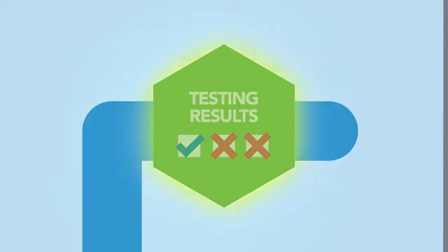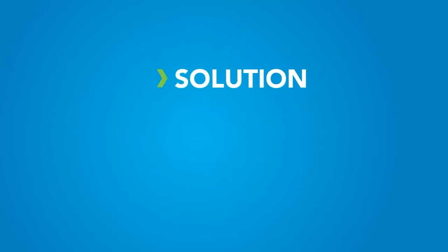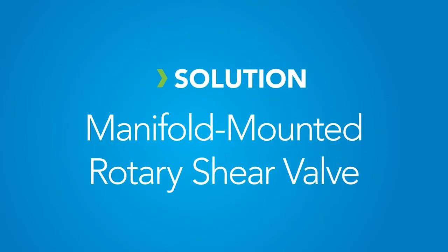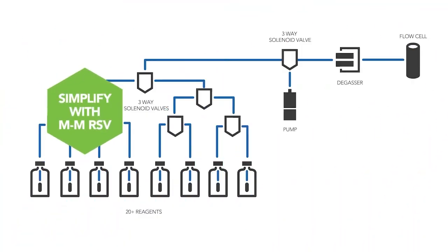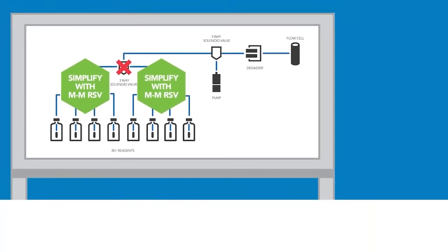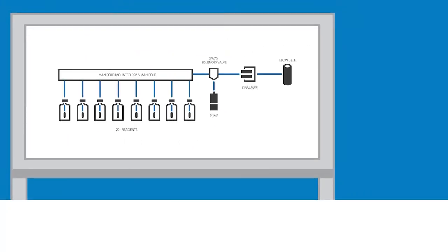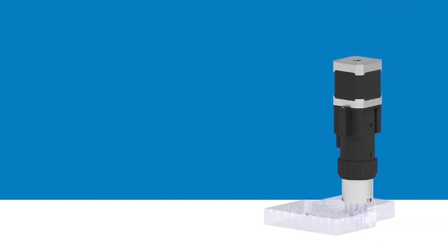There's a way to eliminate complexity and expedite your development timelines by controlling multiple fluidic paths in a single subsystem. Our rotary shear valves, or RSVs, are mounted directly on a custom-designed manifold to create a compact design that eliminates tubing bundles, banks of solenoid valves, and redundant fluid pathways to deliver powerfully reliable outcomes.